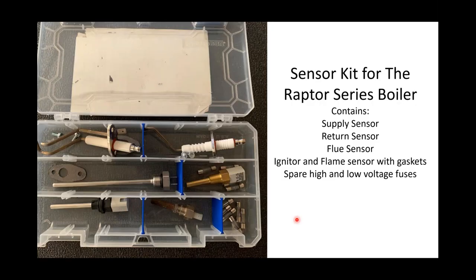So the sensor kit is going to have in it your supply sensor, return sensors, and your flue sensors, all of which should be fine. They shouldn't need to be changed annually. It's just good to have them on hand in case one's reading outside of its range. We'd rather be safe than sorry. The parts that can wear out are your igniter and your flame sensor. We want to make sure they're gapped correctly, that they're not bent out of the way, and that they're clean. That's basically what the steel wool is for, to clean them off.